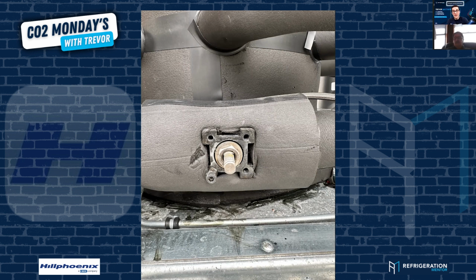And this is very, very important, because maybe the design was a mistake. Not saying it isn't, because it does happen, and maybe you do have to limit it, but most of the time the valve is sized for that specific system by the manufacturer. So changing settings like that can really cause a massive amount of issues. And if you think you have a design issue, contact us. We'll go through it. We'll look at it. Not saying we haven't made some mistakes, but we've got about 1,100 of these systems in the U.S. Awesome. That's amazing. 1,100. Just growing fast.